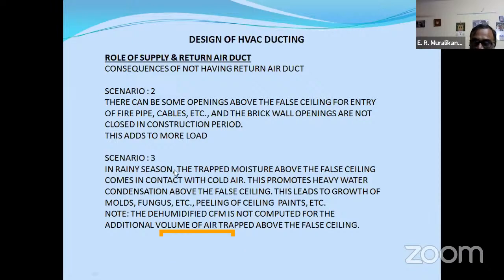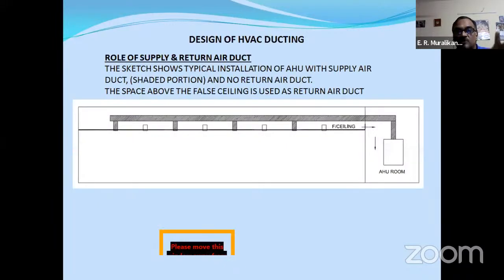Now, in scenario 3, I told you, in the rainy season the trapped moisture above the false ceiling comes in contact with cold air. This promotes heavy water condensation above the false ceiling. This leads to growth of molds, fungus, etc., and peeling of ceiling paints. The dehumidified CFM is not computed for the additional volume of air trapped above the false ceiling. As I told you just a few minutes back, we calculate only up to here. Many people avoid this in calculation, so this load will automatically add to the system.